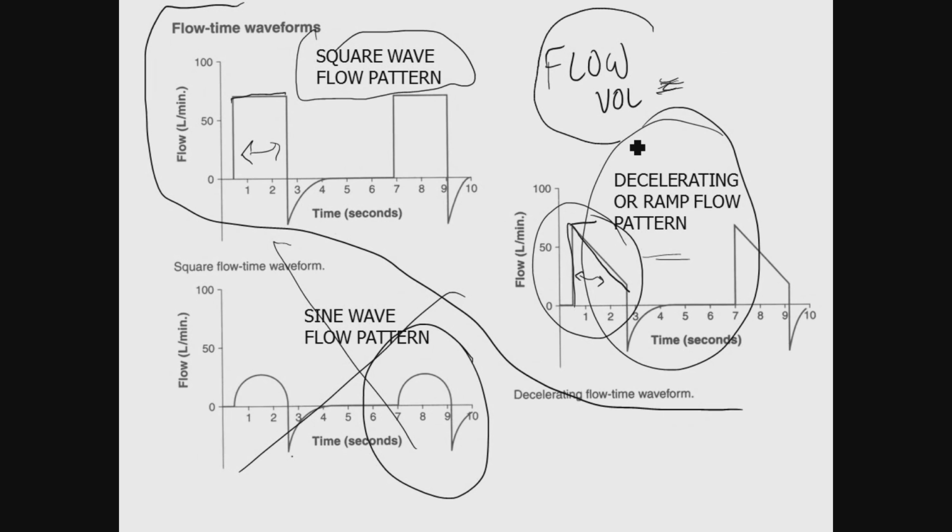Because of that, that's why the dual modes were so attractive. In dual mode, it's a pressure-based breath. Flow is variable. You want more flow? Take more flow. When I used to sell ventilators and teach, I used to grab physicians and put them on ventilators, just that way. Feel this. Now feel this. And to a person, they all said, holy shit, it's a lot easier to ventilate in that pressure-based breath.